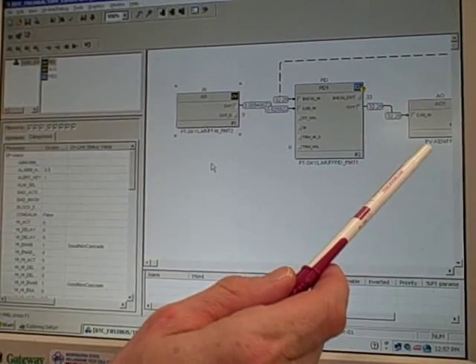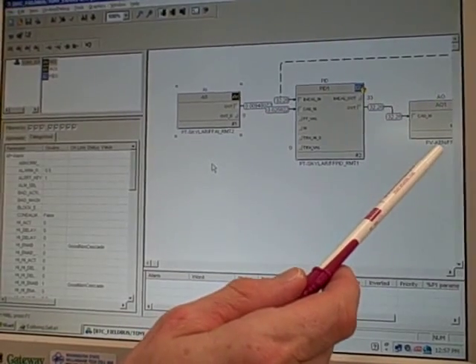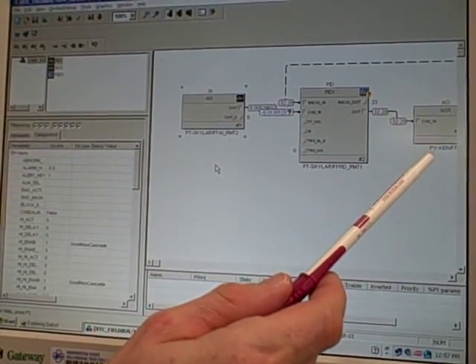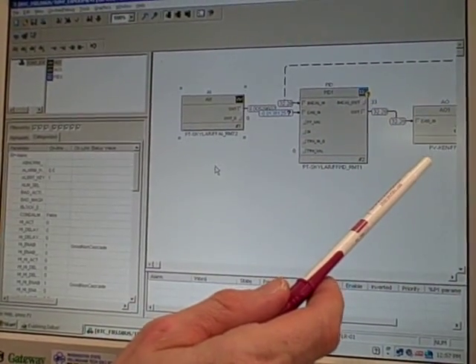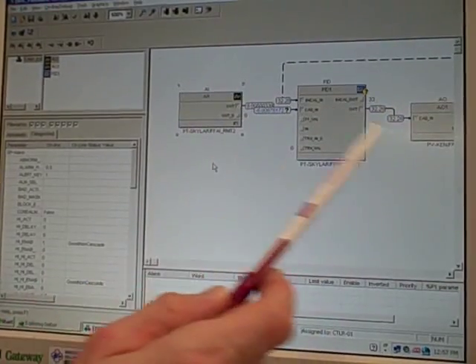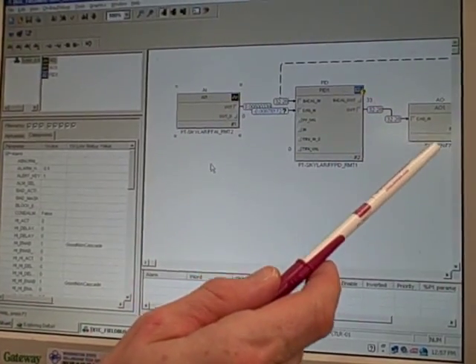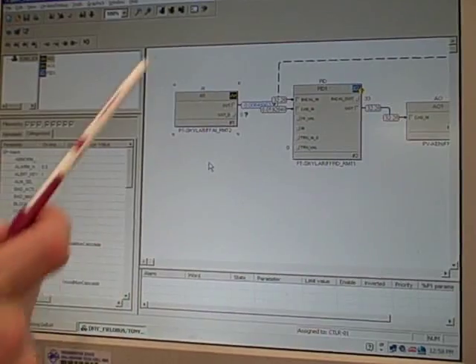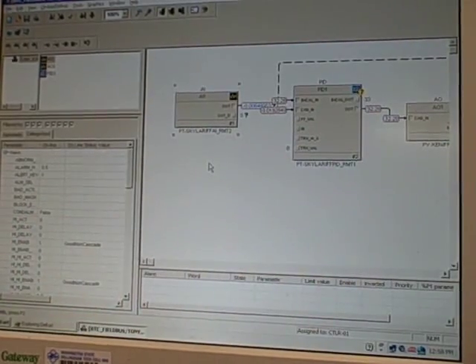Over here it says PV Ken. Well, that's our pressure control valve, and the student's name is Ken. So that one function block is happening inside the valve, and these two function blocks are being executed inside the transmitter.